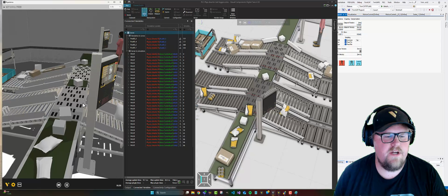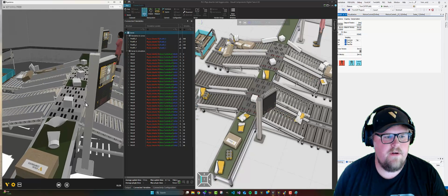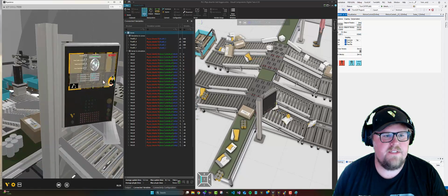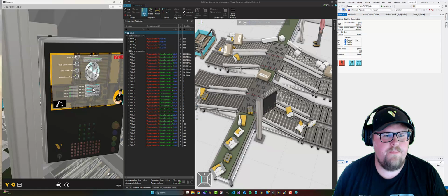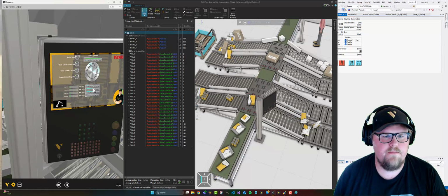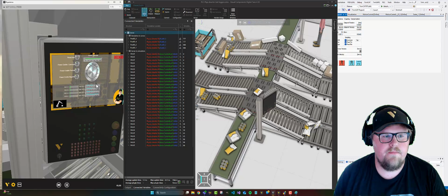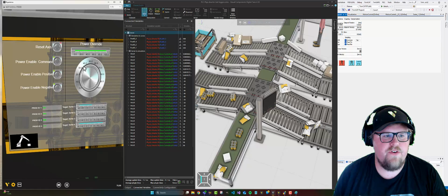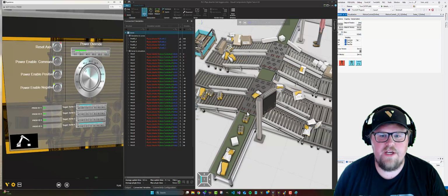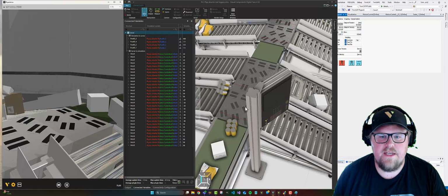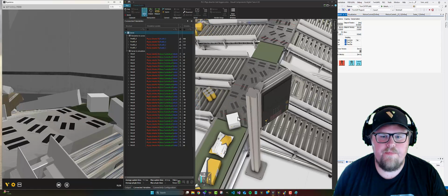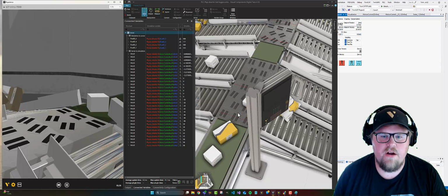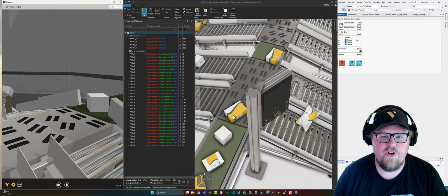Pretty cool stuff. And it basically means that if I now, that was the coffee machine. If I now would decrease, for example, here the override, we can see that the movement of the diverter is much slower, and we are quite often unable to divert the product in time.